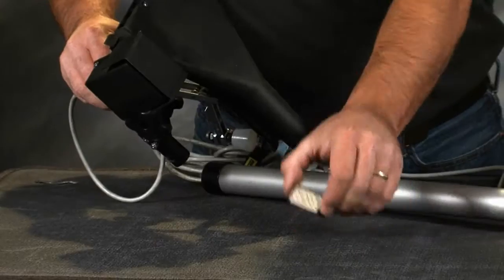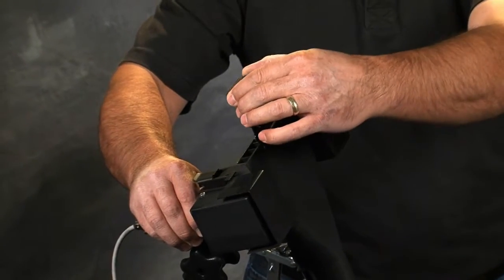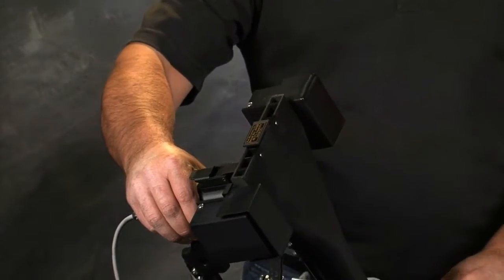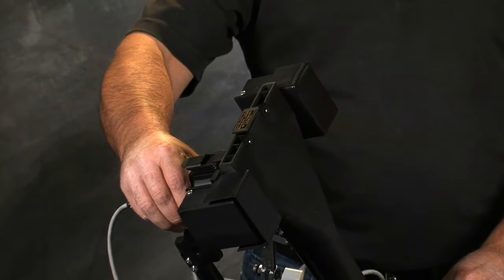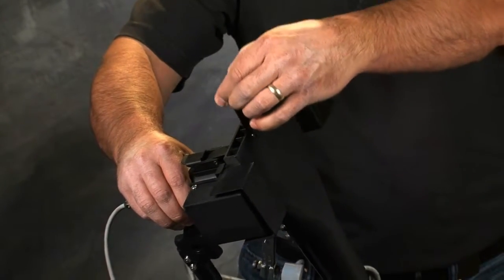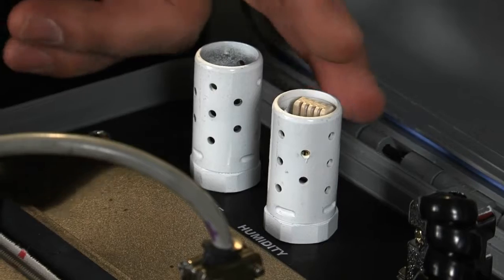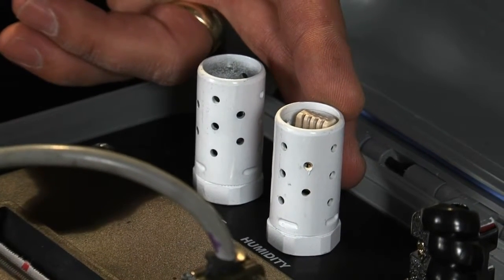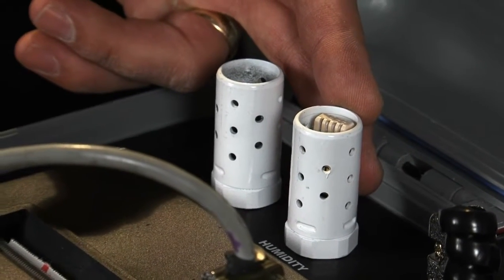We start by calibrating the machine, placing a calibration lens in the back of the machine, running it without the machine in the stack. Along with the temperature and humidity control devices attached to the opacity machine itself, this allows the machine to be at a 0 calibration to compensate for any season or weather changes.